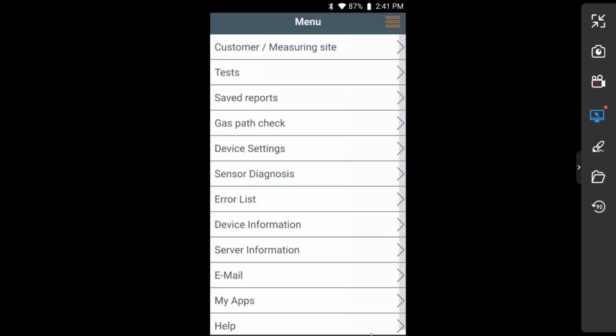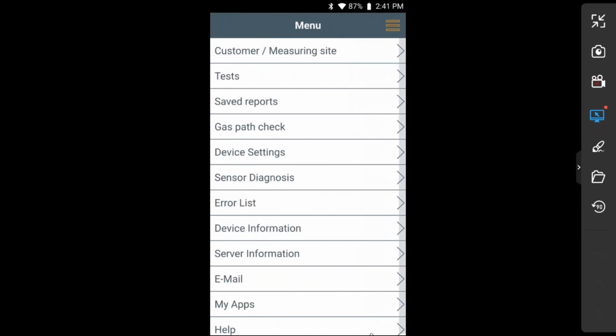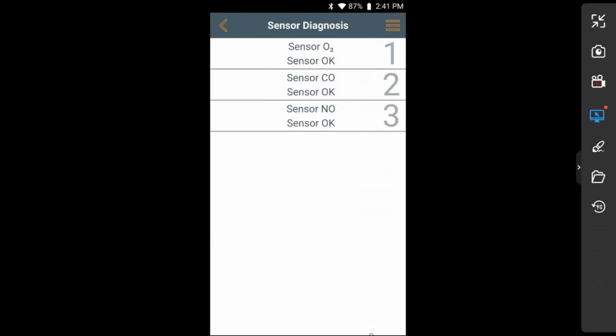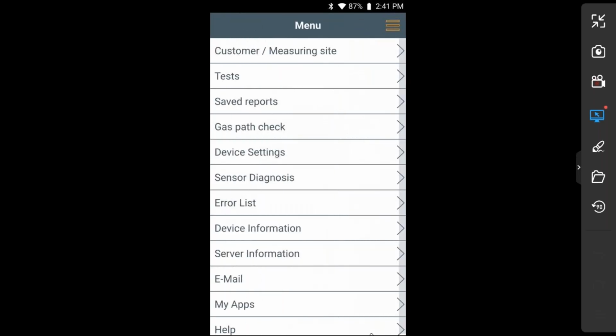This is very easy to use. Error list: it tells you when you have errors. Sensor diagnostics tells you whether your sensors are okay. This instrument has 3 sensors, O2, CO, and NO, and they're all okay. And during the power up, if you have a sensor failure, the instrument is going to tell you that you have a sensor failure during that 30-second power up.